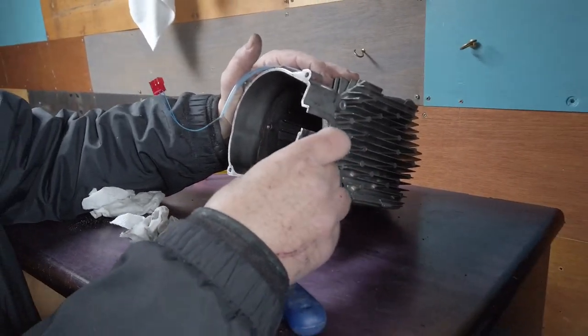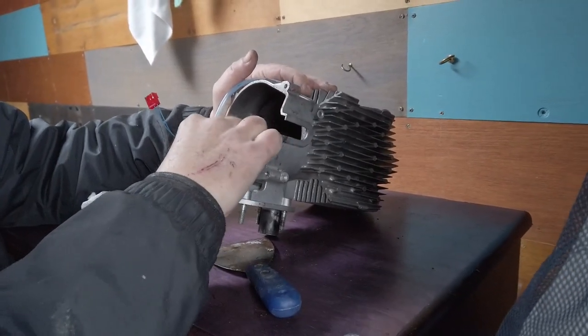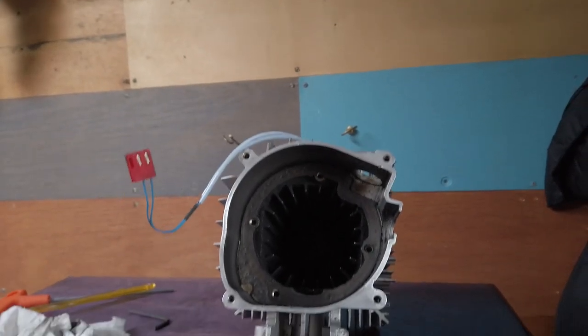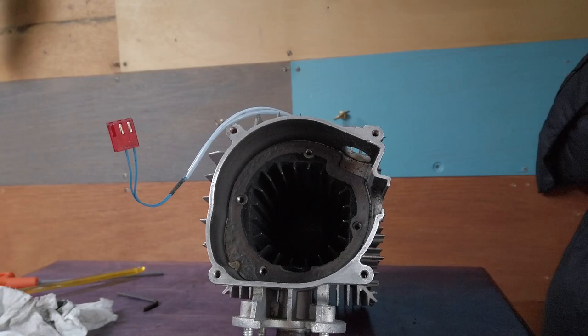Now that could be several reasons why. Your atomizing screen is not working properly, or somebody bumped up the pump settings or what have you. Full of soot in there, but looking okay on that part of the chamber.